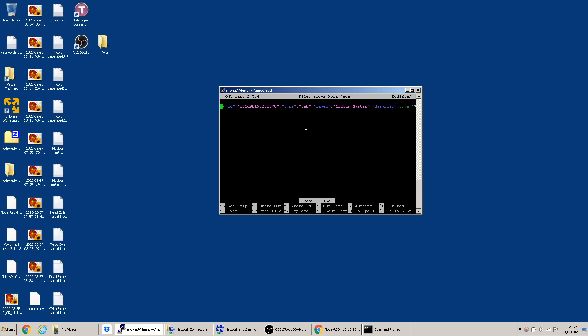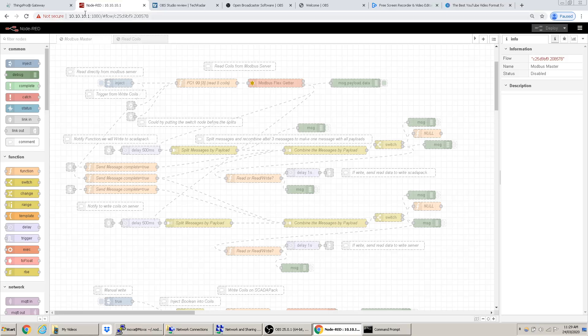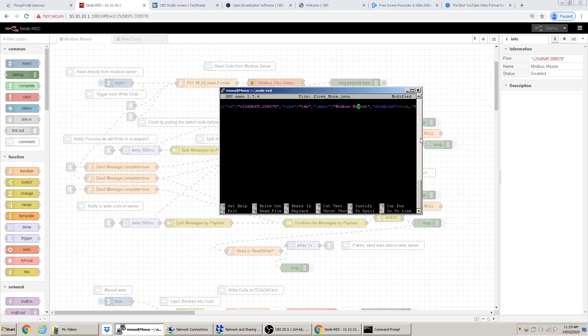This is the flows file. You can see flows like 'Modbus Master' listed here — this flow is currently disabled. If Node-RED is crashing, an easy fix is to find the flow and change 'disabled' to 'true'. If it's false and there are incorrect details like the port or IP, that can cause the crash. Do the same for other flows like 'read coils'.